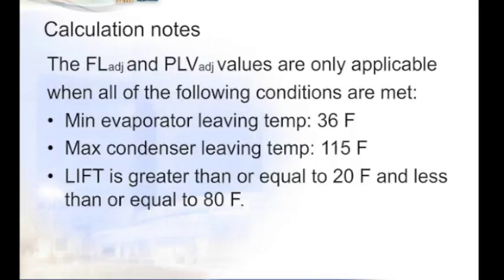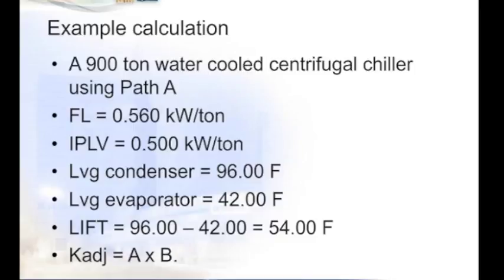So, an example. Suppose a project has a 900-ton water-cooled centrifugal chiller. We choose to use Path A because we believe it will operate at or near full load. From Table 6.8.1C, for a chiller greater than 600 tons, the full load value is 0.560 kW per ton, and the IPLV is 0.5 kW per ton. We're choosing to have this equipment operate with a leaving condenser fluid temperature of 96 degrees and a leaving fluid temperature from the evaporator at 42 degrees. So if we calculate the lift, 96 minus 42 will give us 54 degrees. And using that, we can now calculate the adjusted K value, but first having to calculate the A and B portions.